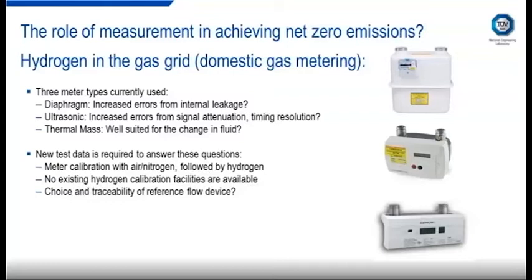But you could imagine with a variable mixture, if hydrogen is injected into the gas grid, then you would have to continuously update the fluid properties or work within a limited range. So this is all not speculation, but we anticipate reasons for increased errors for each of these meters. But what we really need right now is evidence. So we need to have a test program to actually get that evidence. And this is a problem because there's no existing facilities that can do these tests. And if you are to build one, where do you start? I mean, what do you use as your reference device for hydrogen if there isn't any obvious choices?